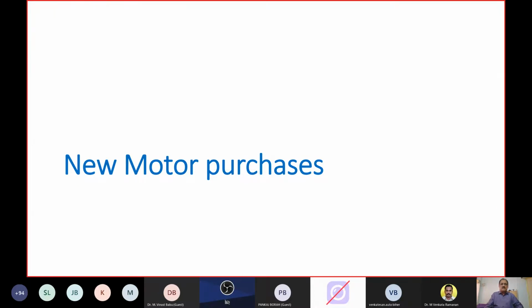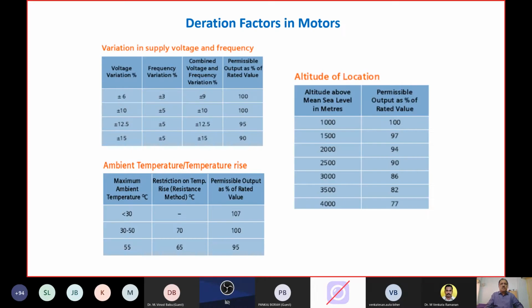So let's look at new purchase of motors. Then we'll look at replacement of motors and the speed change. So those are the future topics. For a new motor purchase, we have to consider the derating factors in motors. Derating factors will be because of voltage variation. Typically up to plus or minus 10% voltage variation, 5% frequency variation, and plus or minus 10% combined voltage and frequency. Supposing you take 7% variation in voltage, 3% is the variation permitted in frequency in order to achieve this 10% combined. So up to this level, the motor need not be derated.